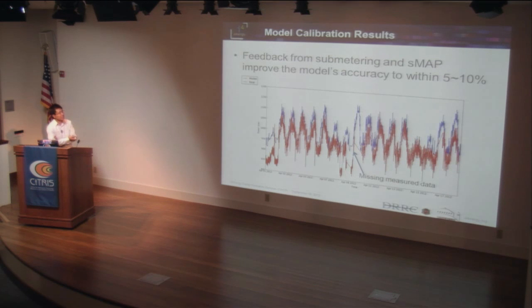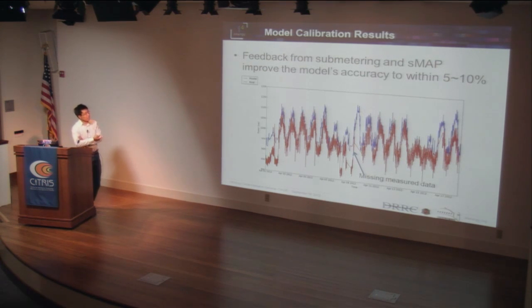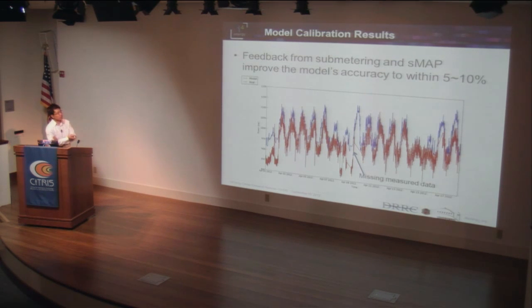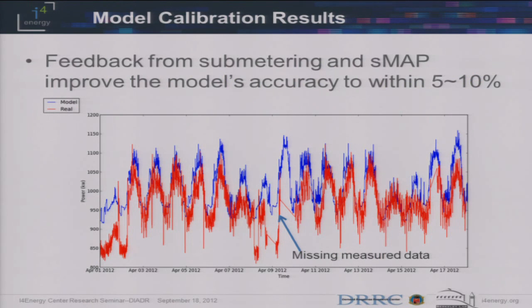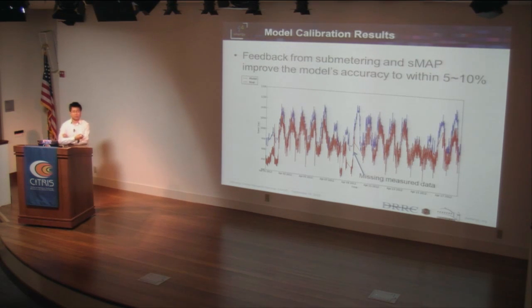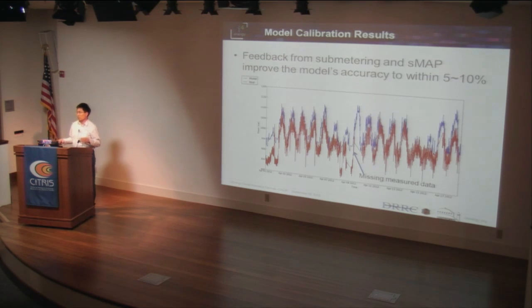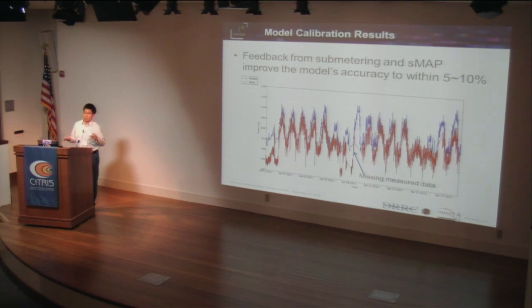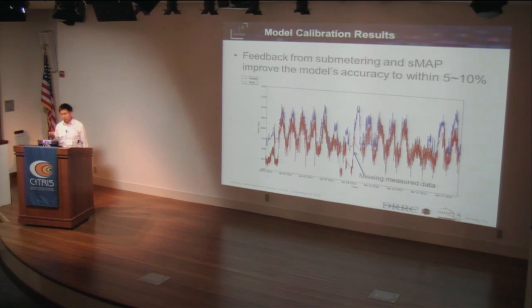Here are the general results comparing the real measured data. The blue line is the model simulation output from EPLUS, and the red line is the real data from CITRIS. There is some missing data, but generally we can improve the model accuracy to within 5 to 10%. The purpose of improving model accuracy is for the demand response application — our target is to achieve 30% demand reduction. A model with more than 20% error is a weak model, and the results it provides to the building manager could lead to wrong decisions when implementing optimal control strategies.